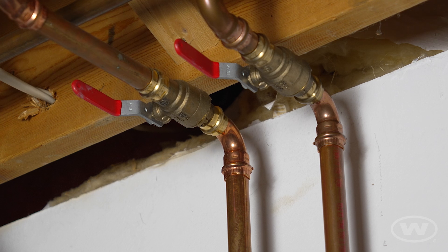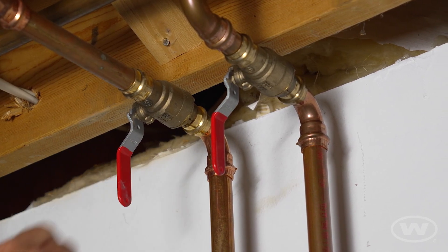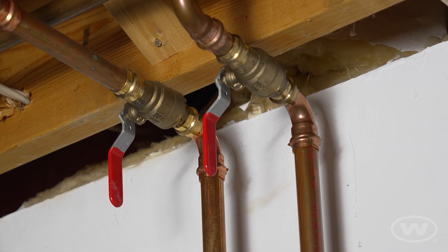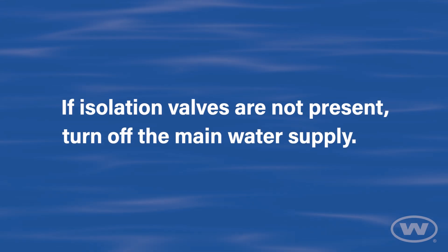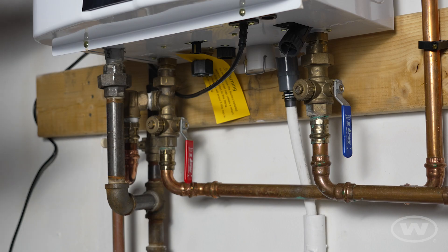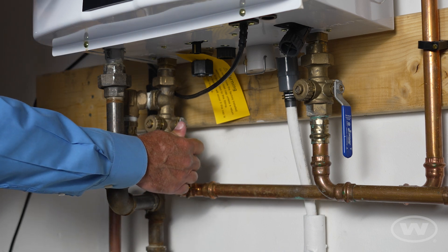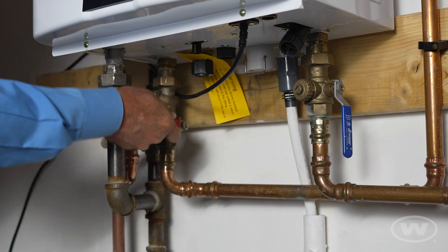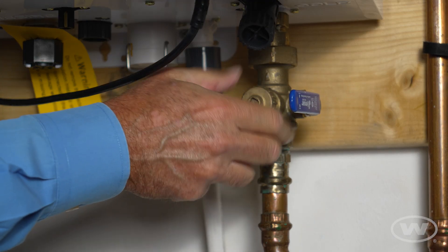Turn off the hot and cold isolation valves by turning the supply line valves to the closed position. If isolation valves are not present, turn off the main water supply. Locate the service valves, which are typically located under the tankless heater. With the service valves in the closed position, remove the service caps from the hot and cold service valves.